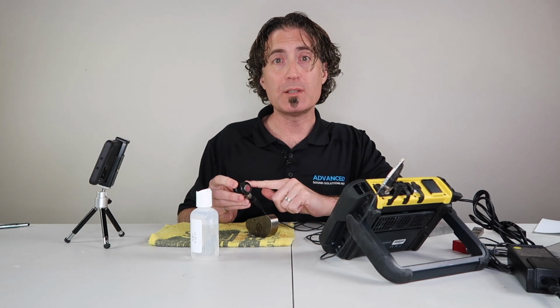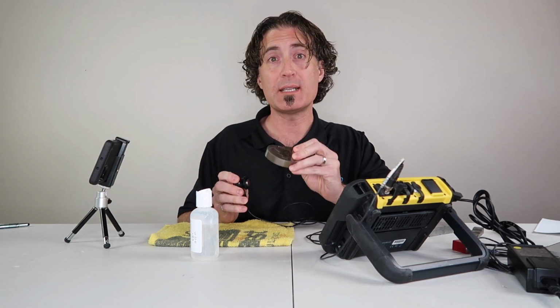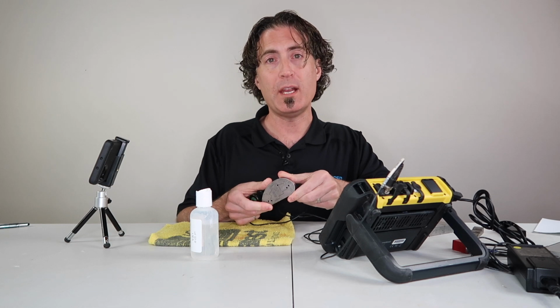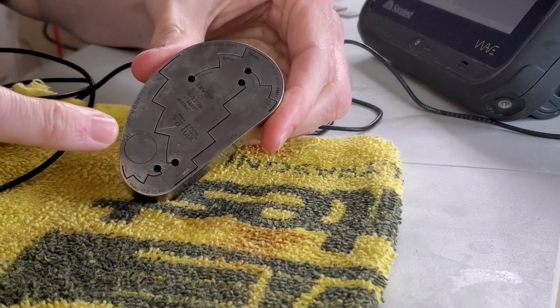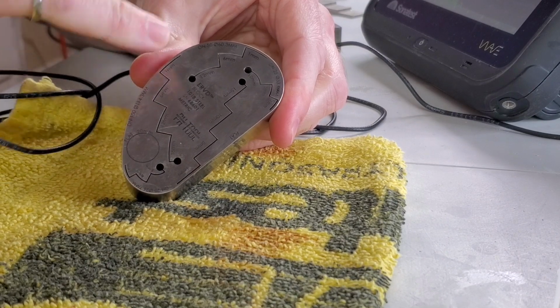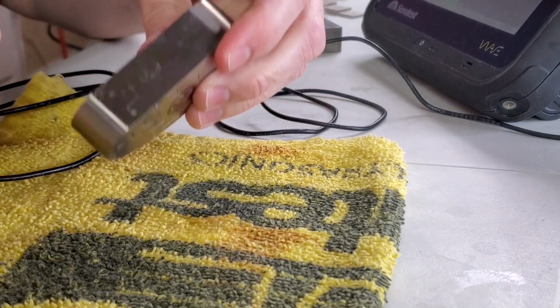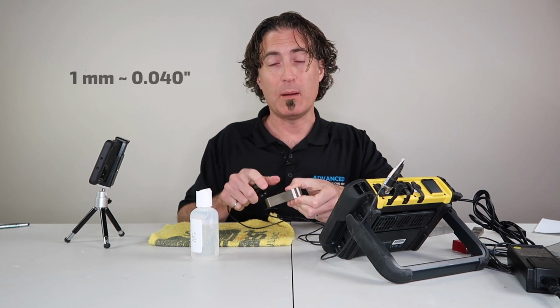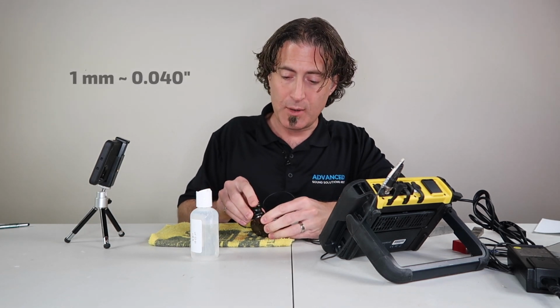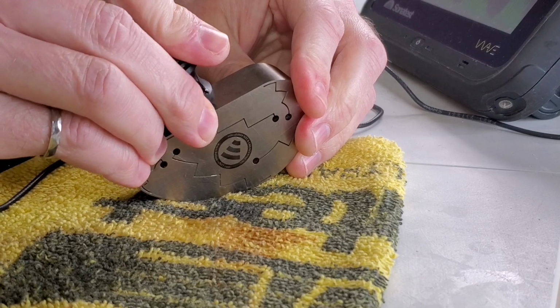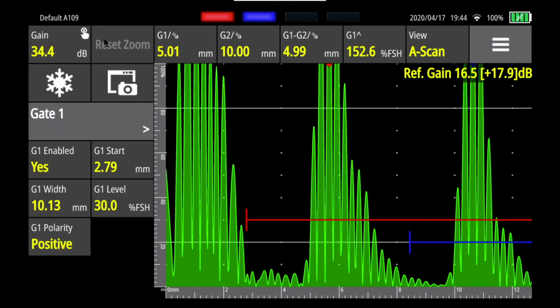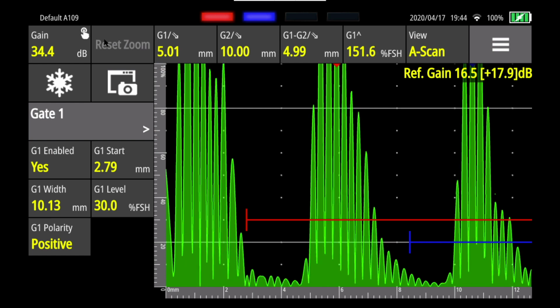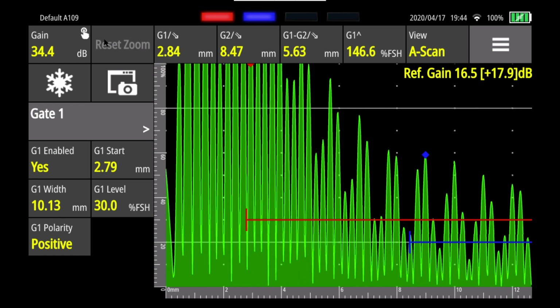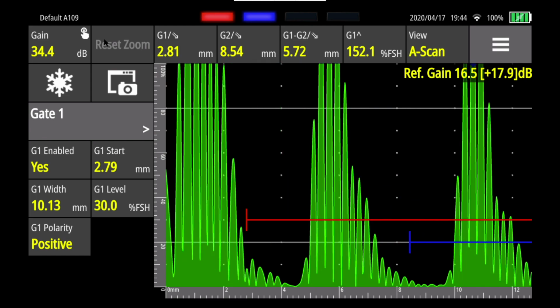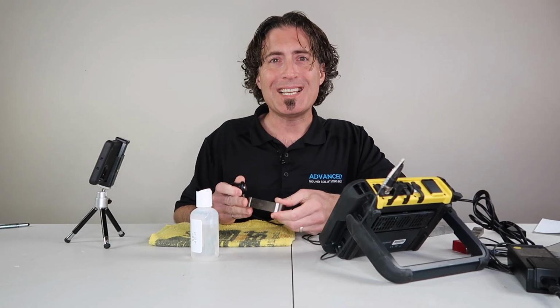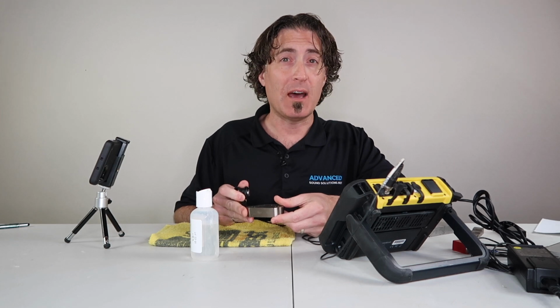I'm going to take this 5 megahertz probe and put it on a steel step wedge. In this case, I'm going to use an ERVD, or extended range variable diameter block. It's basically a flat wedge and then 4 different curved wedges built into one block. And it's going to serve us well here because it does have a 1 millimeter step on it. So I'll take the probe and put it on the 5 millimeter step. And you can see here that the dead zone is about 2.5 or 3 millimeters, and it doesn't look like I'm going to be able to resolve the 1 millimeter step at all. So in this case, with this probe on a nice clean steel surface, my dead zone is about 2.5 millimeters.